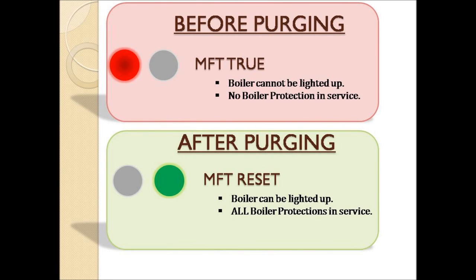This picture clearly depicts the condition before and after boiler purging. Before boiler purging, MFT — Master Fuel Trip — is in the true condition. When MFT is in the true state, it does not allow the boiler to be lit up, and there will be no boiler protection in service. After completion of the 5-minute purge cycle, MFT resets. As MFT is no longer persisting, we can go ahead for boiler light up and all boiler protections are in service. We will discuss boiler light up in the next tutorial.